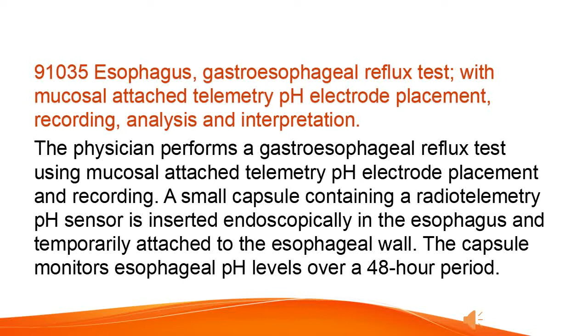This information is transmitted to an external pager-sized receiver worn by the patient that records pH levels. After the 48-hour testing period, the data is downloaded from the receiver to a computer that contains software for analyzing pH levels. The physician provides a written interpretation of the computer analysis. The capsule does not need to be removed as it spontaneously detaches within 7 to 10 days and passes through the digestive tract.